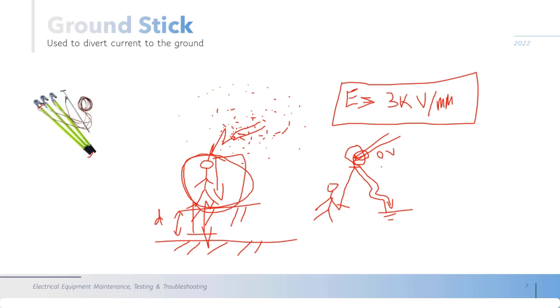volts. Practically the line will take so long to reach 0 volts, and sometimes you need to work quickly, so you keep the ground wire there and you work while the voltage is discharging, and you count sometimes until the voltage discharges, let's suppose, to 1 kV. At this voltage you can use gloves to touch the line and work safely even while the line is discharging to the ground. So this will avoid a long outage of the line.